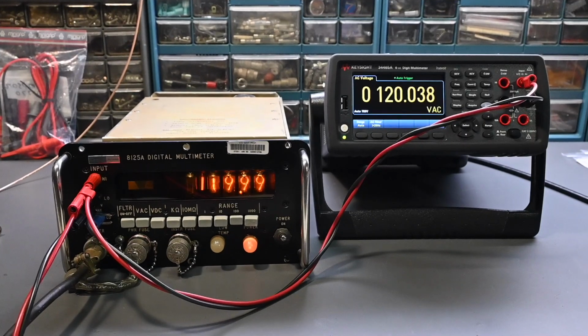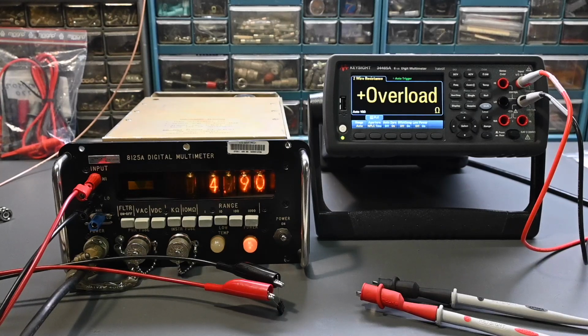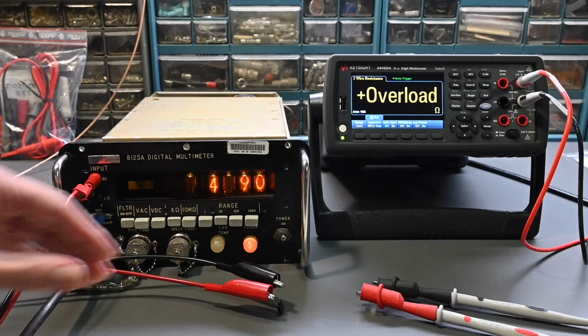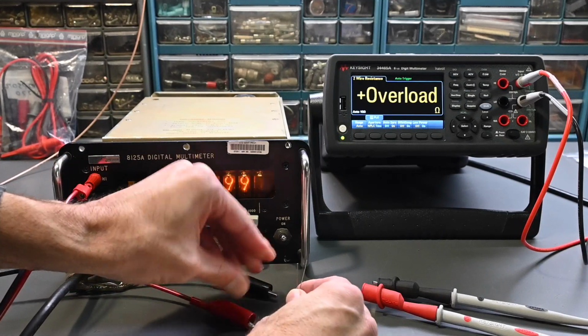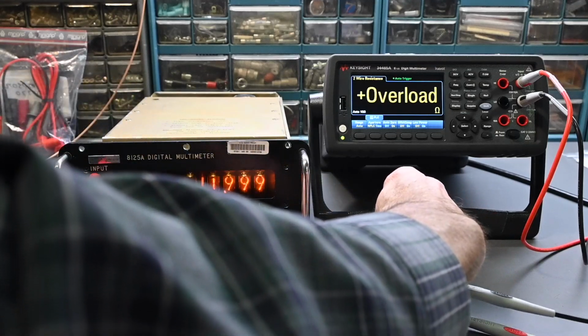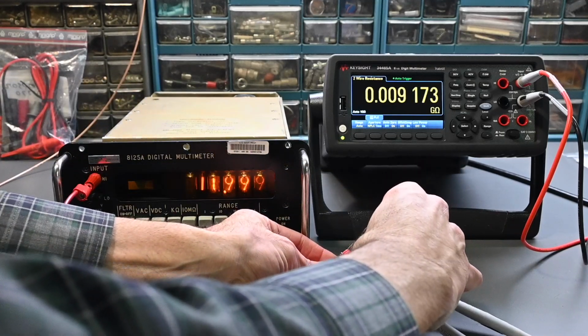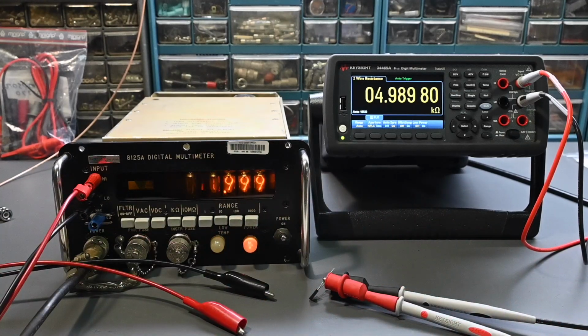All right, and there's the reading off of my isolation transformer. So I'm sitting 119.99, so that's right at 120 volts. And the Keysight is showing 120 volts. So no problems whatsoever. All right, now I have a precision 4.99 k ohm resistor connected to the Fluke 8125A, and you can see the display, 4.99 k ohms, so the reading is spot on. So now let's see what the Keysight shows, see if the readings agree. No problems, 4.9898. Very, very close, so no issues there.